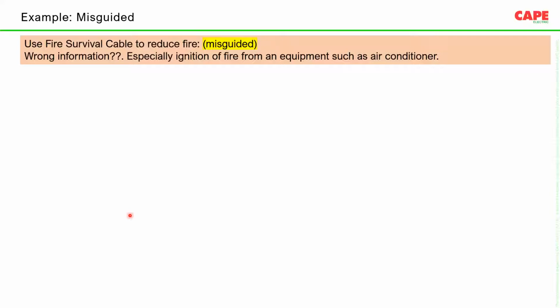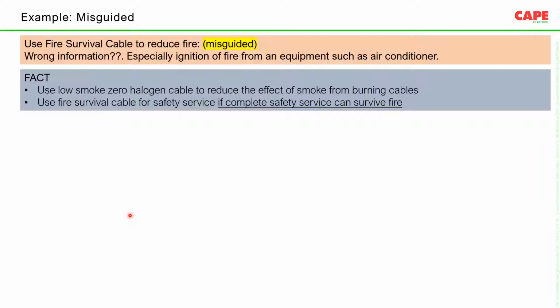The wire should withstand the fire. Actually, this is not the correct information. The fact is, for certain applications in a building, especially for fire survival or fire safety service, safety service is a place where people should escape in case of a fire. Electrical installation in the safety service shall withstand for a certain time, or it has to survive fire until a certain time.